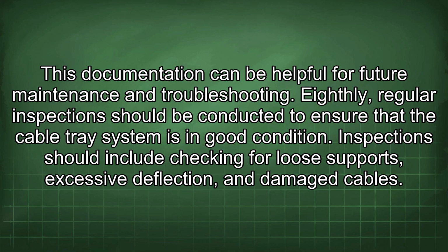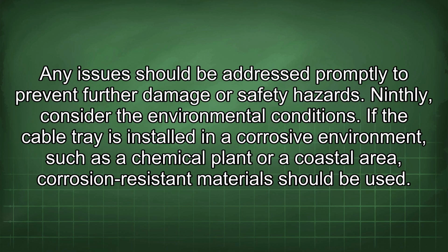Eighthly, regular inspections should be conducted to ensure that the cable tray system is in good condition. Inspections should include checking for loose supports, excessive deflection, and damaged cables. Any issues should be addressed promptly to prevent further damage or safety hazards.